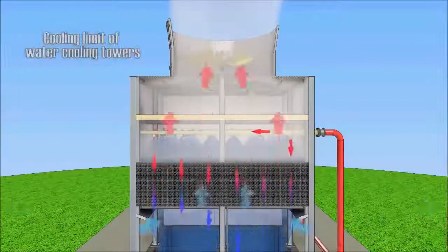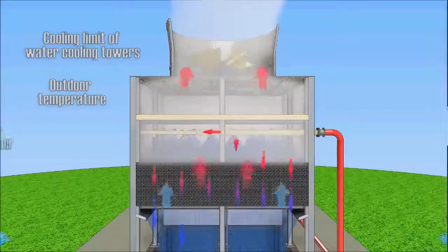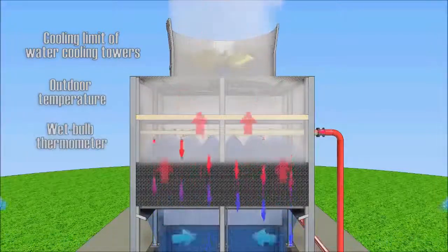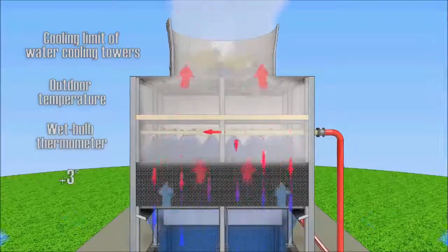In practice, the limit of cooling is the wet bulb temperature plus three degrees Celsius.